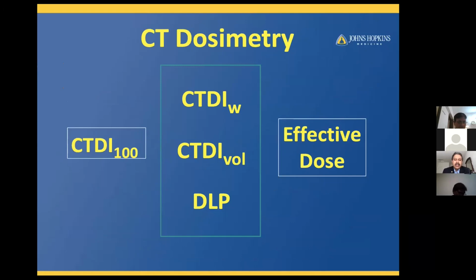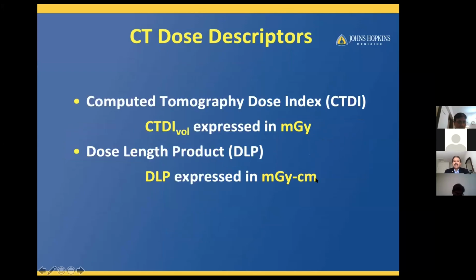So in comparison, what we do here is CTDI-100 is what we measure, and we calculate CTDI weighted, and you take into account the pitch value, which is called the CTDI volume. You multiply that by the scan length, and we get dose length product. From here, we do a lot of estimation to arrive at the effective dose.